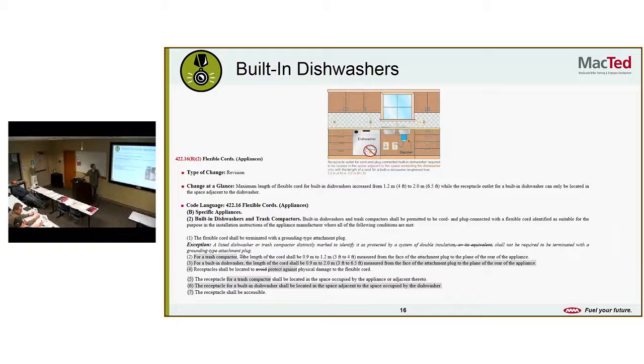Built-in dishwashers. This was something I just went through. So now, if you're putting in a dishwasher, they've increased the length of the cord. Most dishwashers have a plug-in on them, like a whip. You plug it in. They've increased the length of the cord from 4 feet to 6.5 feet. But they've also increased the requirement, so now you can't have a plug-in right behind the dishwasher. It has to be in the next bay over. Readily accessible. Yeah, for leaks. Don't want it in a wet condition? Yeah, readily accessible, and accessible.